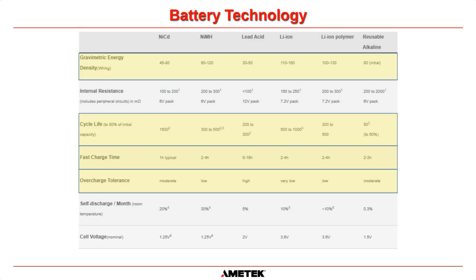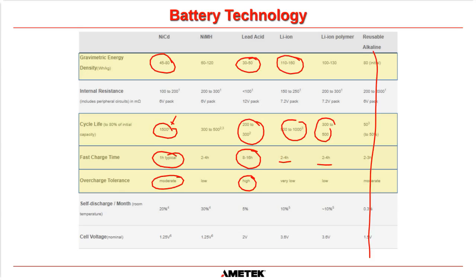It says lead acids have a high overcharge tolerance. I don't think that's necessarily true, especially for a valve regulated, a VRLA battery. If you overcharge a VRLA battery, it can go into thermal runaway if left too long. So for a vented cell that has electrolytes similar to the NiCad, yes, it has high overcharge tolerance, without a doubt, because once again, all that happens is that it boils off more water in the process.